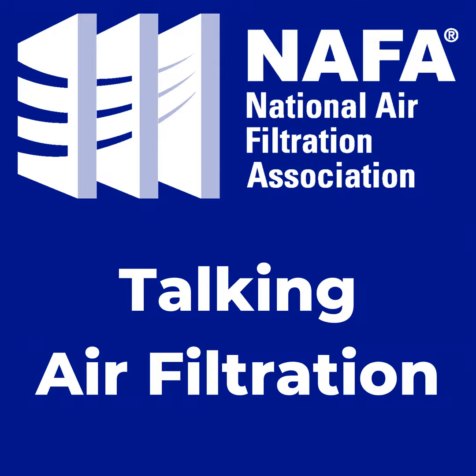But why do we see that difficulty in performance compared to other traditional MERV 13, 14, 15 type medias? It's the electrostatic charge. It's something that's always discussed in these talks, where we know the electrostatic charge is present, and that a MERV 15 filter with electrostatic charge might not actually be a MERV 15 filter, because the electrostatic charge is pulling the particles out of the air and attaching them to the fibers. It's going to degrade in performance over time.